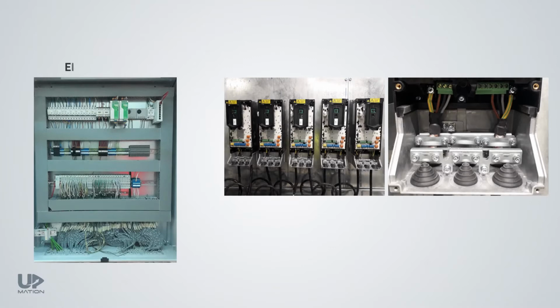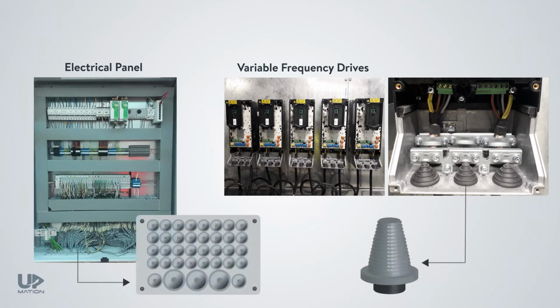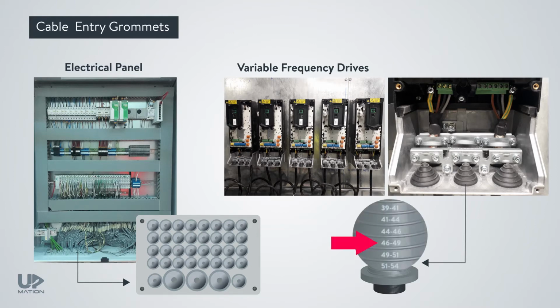As a side note, in some electrical panels, motor boxes, or VFD panels, we might see some pre-installed pyramid plastic parts known as cable entry grommets. These are for routing the large or unknown size cables and are more flexible compared to conventional cable glands. As you see, the diameters are marked on them so that you can cut them from the appropriate place.